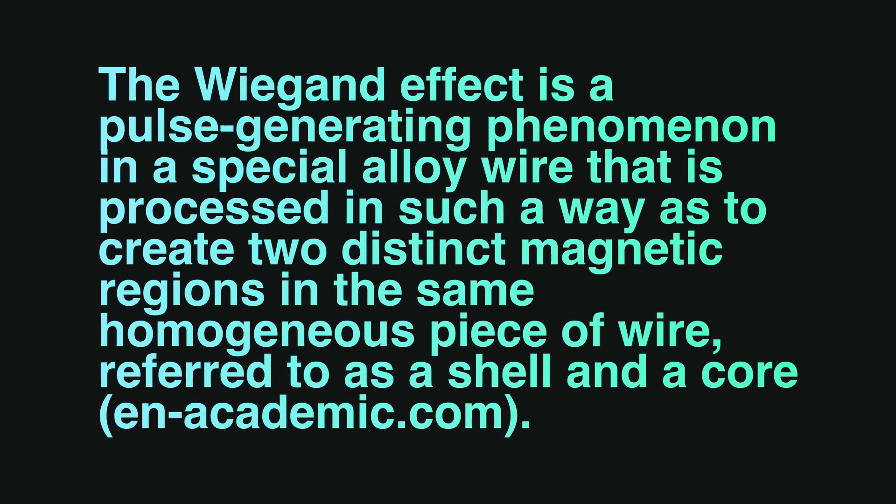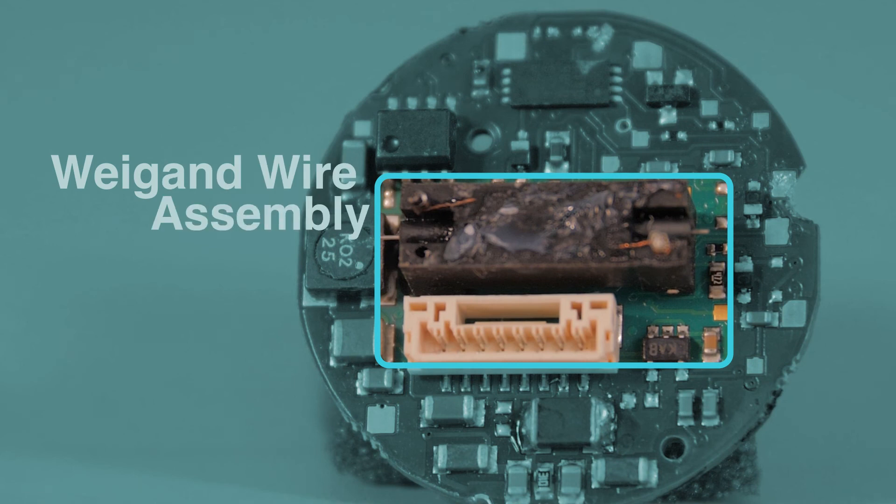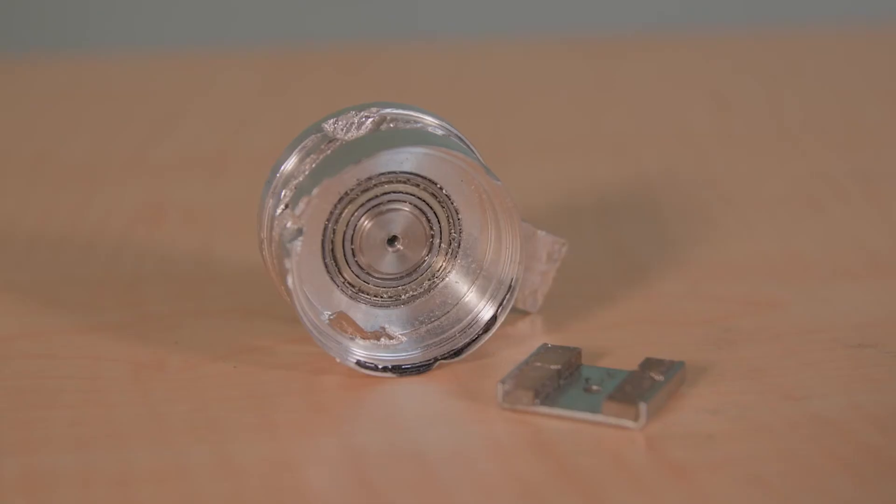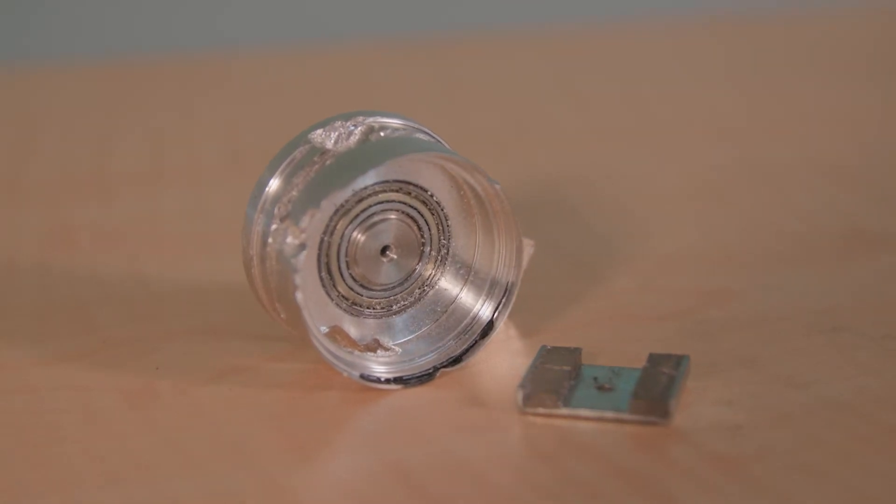The typical way of taking advantage of the Wiegand effect is to put the Wiegand wire in the middle of a coil, which is what you'll find on the PCB inside the Avtron absolute encoder. You find two magnets attached to the spinning shaft to generate the pulses.